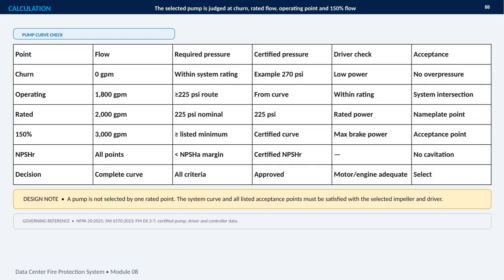curve verification. This slide explains how the selected fire pump is evaluated across its complete performance curve, rather than at only one rated point. The key idea is that acceptance depends on satisfying every listed condition: churn, operating flow, rated flow, and 150% flow. At churn or zero flow, the system must remain within its pressure rating, with no unacceptable overpressure. At the operating point, the pump must meet the required route pressure at 1,800 gallons per minute and intersect the system curve. The rated point confirms the nominal 2,000 gallon per minute duty at 225 psi, while the 150% point checks the pump at 3,000 gallons per minute against the listed minimum pressure and maximum brake power.